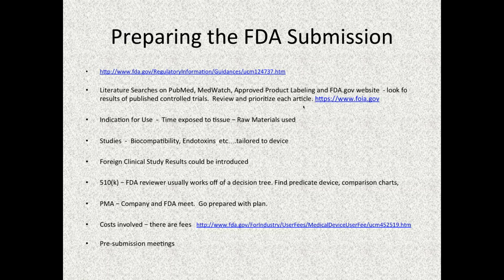Indications for use are going to be determined by the time exposed to the tissue and what the raw materials are. Those are the two big ones. Your classification is going to be determined by this: indication for use, time exposed to tissue, and your raw materials. So stay in the category where they've seen the raw materials before, and where the time exposed to tissue is explained. That's not a 510K killer. Your indication for use can move you around a lot as far as what evidence you're going to have to supply. The studies that you'll be involved in, biocompatibility is a big one.